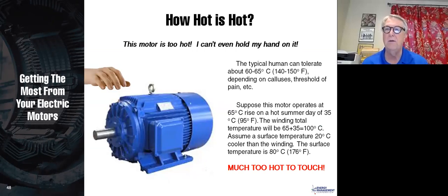The typical human can tolerate about 60 to 65 degrees centigrade. Let's suppose we have a motor. It's operating at 65 degrees C rise. And remember, even a class B rise is 80. On a hot summer day of 35 degrees, and remember the rated temperature for ambient is actually 40 degrees, we're not anywhere close to the maximum rating of that insulation. The winding total temperature is 65 plus 35 is 100 degrees centigrade. Take 20 degrees off of that because the frame is going to be 20 degrees or so cooler than the inside. And that means the surface temperature will be 80 degrees C.